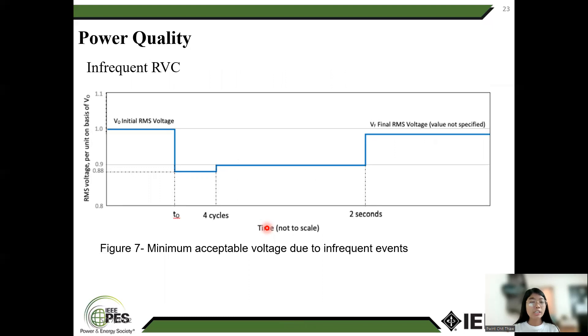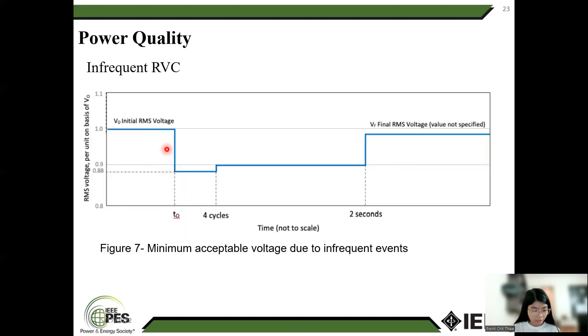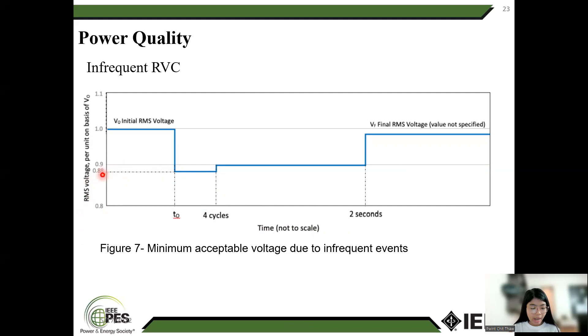Power quality. The figure shows the minimum acceptable voltage due to infrequent events. The initial RMS voltage V0 and final RMS voltage VX shall be within the steady-state nominal rated voltage. The result of the measured voltage at the RPA during an infrequent event shall be equal to or above the value defined by the line beginning at the start and ending N seconds later. For infrequent events, the figure illustrates the IBR limit criteria: the minimum voltage measured at the RPA shall be no less than 0.88 per unit. After 4 cycles, the minimum value shall be no less than 0.9 per unit.